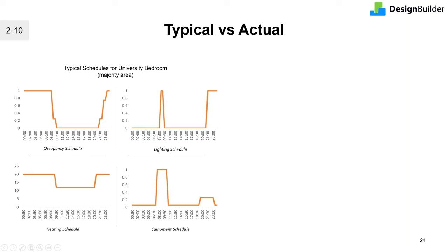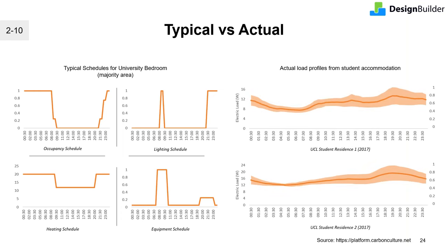However, when developing a model every assumption should be questioned and verified — from yourself and from information gathered from your client and stakeholders. Contrasting typical operational assumptions against a monitored electricity load profile from a couple of actual student residences at University College London provides an interesting insight. What is clearly visible is that the assumed slump during the day in the typical schedule is not evident in these student accommodations. This is pre-pandemic data. Therefore, even projects in the same category may have different operations due to contextual reasons, and a structured discussion with the client is useful to understand typical occupancy, ideally backed up by data rather than guesstimates.